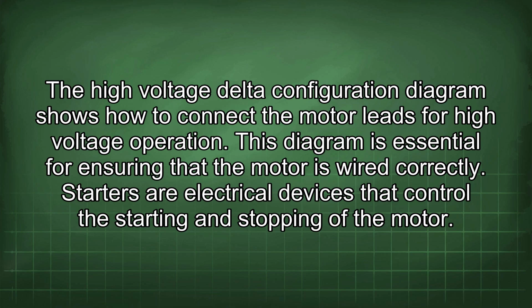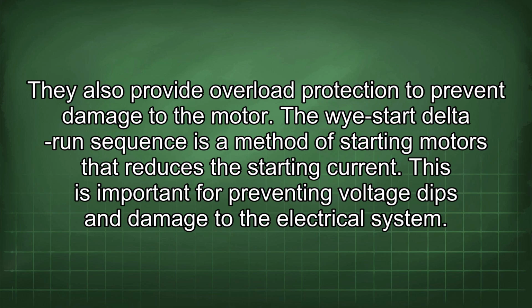Starters are electrical devices that control the starting and stopping of the motor. They also provide overload protection to prevent damage to the motor. The Wye-Start delta run sequence is a method of starting motors that reduces the starting current. This is important for preventing voltage dips and damage to the electrical system.